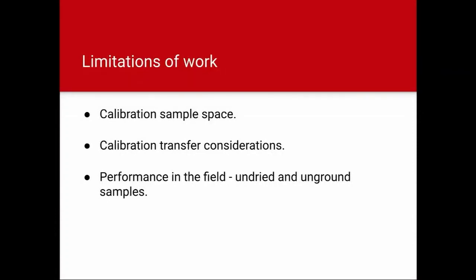The calibration sample space, so we go out and gathering hundreds of samples and running them through wet chemistry and comparing instruments is time consuming and very costly. These papers and our paper haven't considered calibration transfer, so we got this to work on one instrument, but how well does that translate to other instruments of the same manufacturer? We do know that there is an influence of instrument to instrument variability even on the original FOSS instruments and on the diode array instruments for certain. I would expect these instruments to have that same type of calibration transfer issue. And can we use the same techniques to mitigate that? I would suspect we can, as we do on the other instruments.